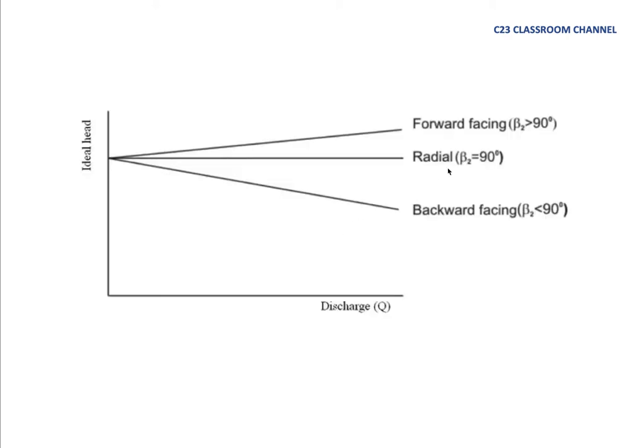Why is the blade type important? Because blade angle will give you different curves. If we have a curve of ideal head and discharge, we find that if we use backward facing, as we increase the discharge, the ideal head—the capability of that pump to transfer water from low to high level—will decrease. For radial, it doesn't significantly change, but for forward blade, if we increase the discharge or flow rate inside the pump, the ideal head can increase.